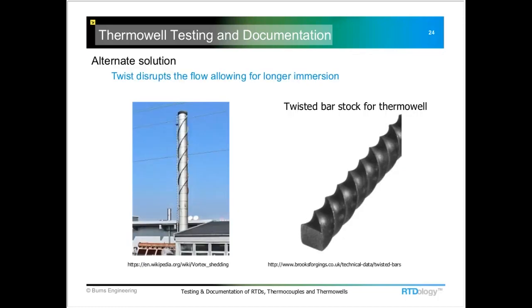One of the ways that we can get around not having enough immersion but still passing the wake frequency and strength calculations is to do a little something to the well to disrupt that flow. You've seen some smokestacks out in industrial areas. They've got this little spiral wrap around them. Well, what they're trying to do is to disturb the wind flow around that so we don't get this wake frequency issue and cause that smokestack to vibrate.